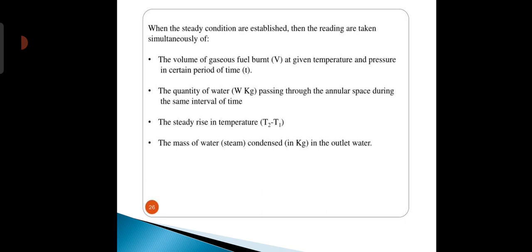When the steady conditions are established, then the readings are taken simultaneously of the volume of gas fuel burned V at given temperature and pressure in a certain period of time T, the quantity of water W kg passing through the annular space during the same interval of time, the steady rise in temperature T2 minus T1, and the mass of water or steam condensed in kg in the outlet water.